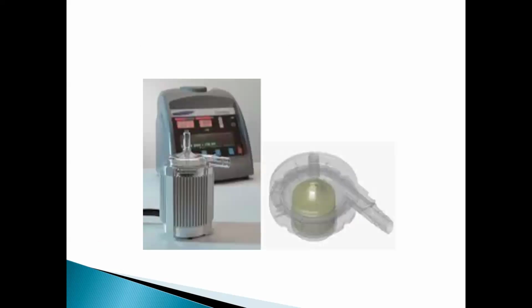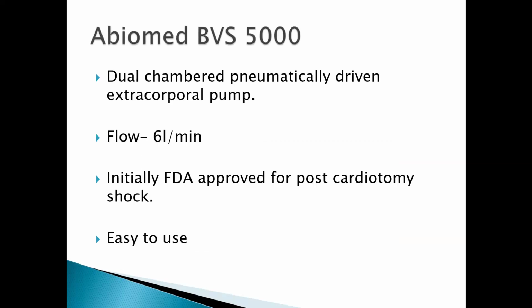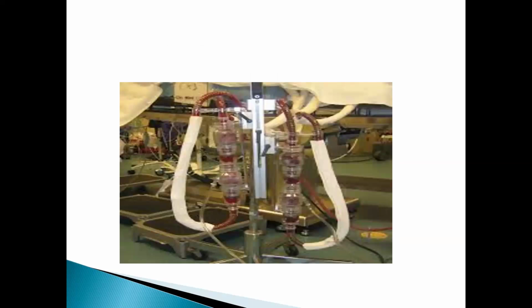Please, next slide. This is just a picture of what a Levitronix CentriMag looks like. Next slide, please. Then the Abiomed BVS 5000. This is still part of the short-term ventricular assist devices. It works through a dual-chambered, pneumatically driven extracorporeal pump. It has a flow rate of about 6 liters per minute. Initially, the FDA approved this for post-cardiotomy shock, and it's an easy machine to use. This is what it looks like. So you connect it, and you can actually...